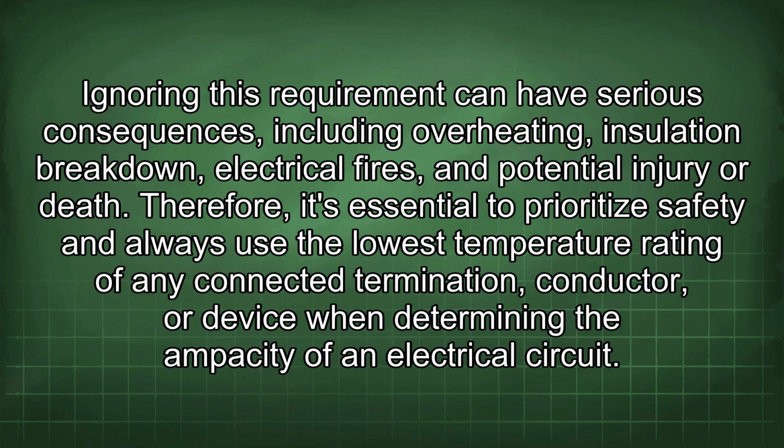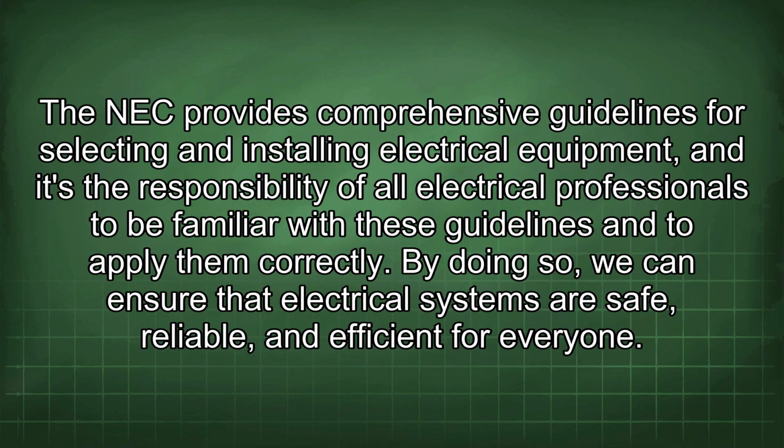Therefore, it's essential to prioritize safety and always use the lowest temperature rating of any connected termination, conductor, or device when determining the ampacity of an electrical circuit. The NEC provides comprehensive guidelines for selecting and installing electrical equipment, and it's the responsibility of all electrical professionals to be familiar with these guidelines and to apply them correctly. By doing so, we can ensure that electrical systems are safe, reliable, and efficient for everyone.